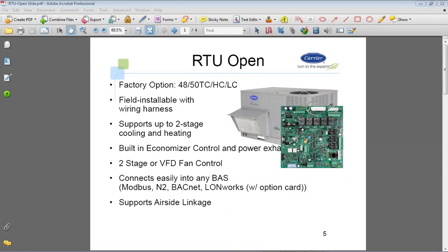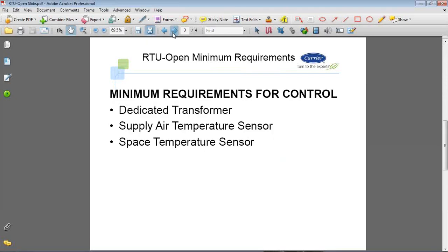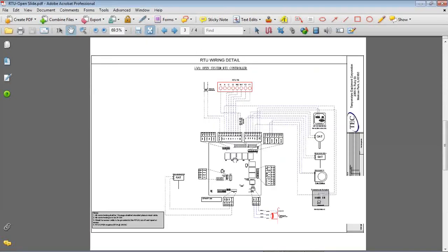This is a Molex connection from our rooftop controller that we provide a wiring harness to that plugs directly into there and can wire to the thermostat terminal board. So if we look again, we have two Molex plugs, and they connect. You wire right to the RTU thermostat terminal board, your common, your G, your Y1, your W1, and then you have all these other sensors. Not all of them are required, but these would just be options of how you can wire them in.